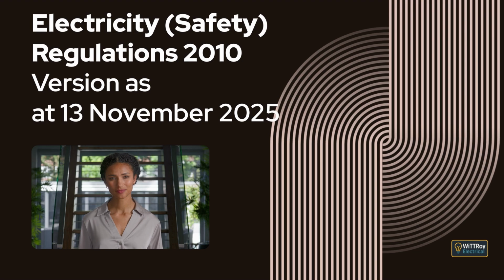Reg 74C time when electrical safety certificate to be issued. This regulation explains that an electrical safety certificate must be issued as soon as practicable after the installation or part installation is connected to a power supply, and in all cases no later than 20 working days after connection. Reg 74D offences relating to electrical safety certificates. This regulation explains that a person commits an offence and is liable on conviction to a Level 2 penalty if they issue an electrical safety certificate without being properly satisfied, issue a certificate that does not meet regulatory requirements, or fail to issue a required electrical safety certificate within the required time.